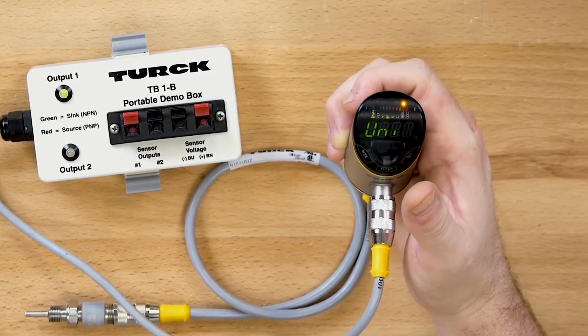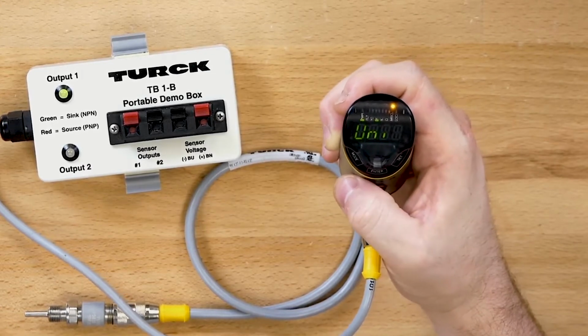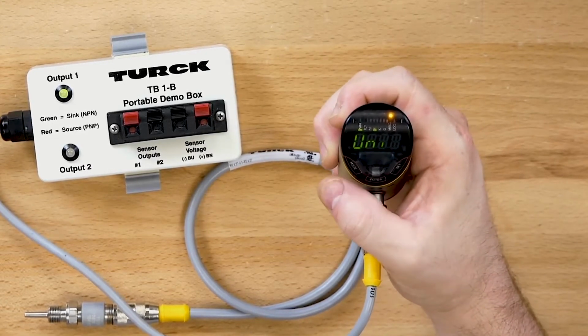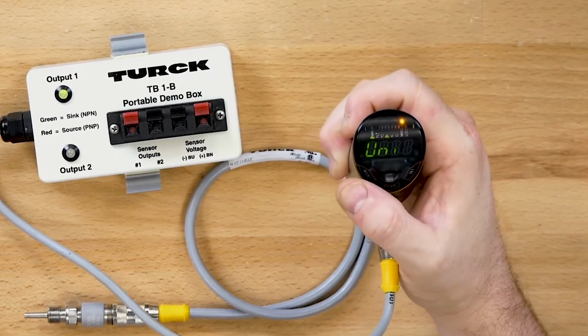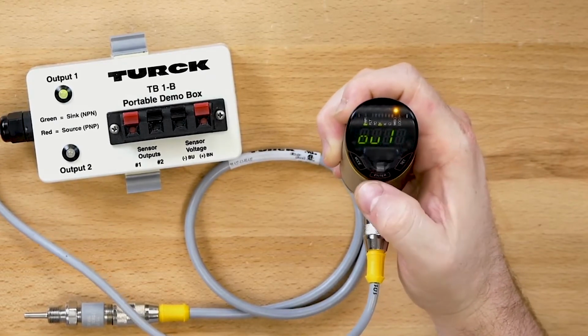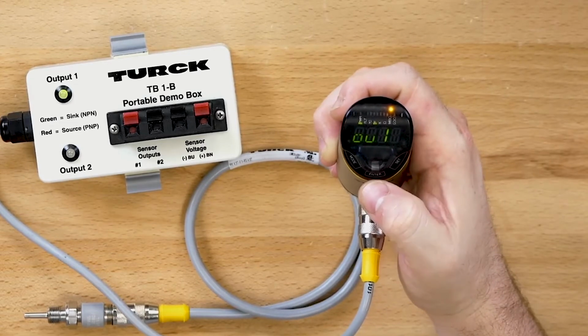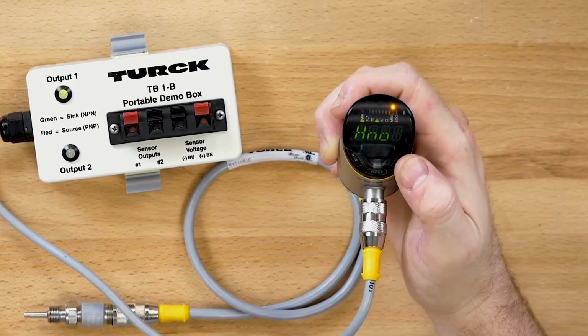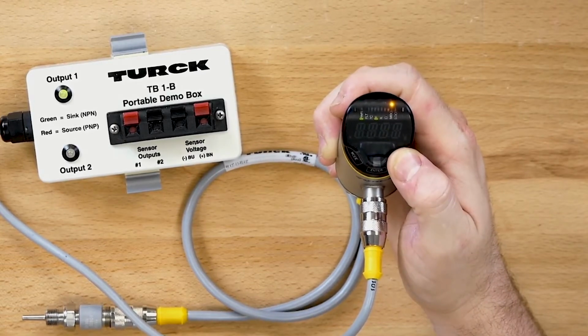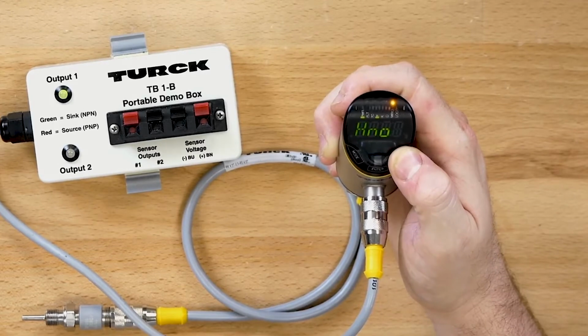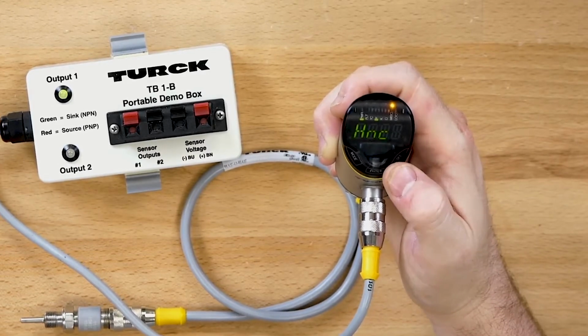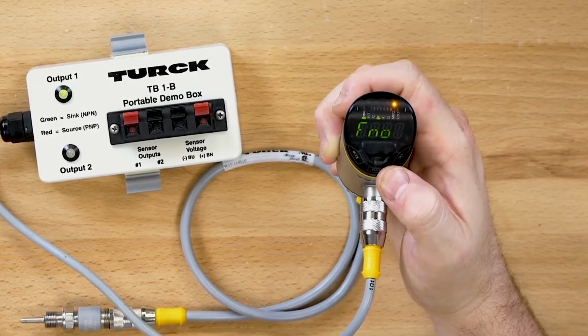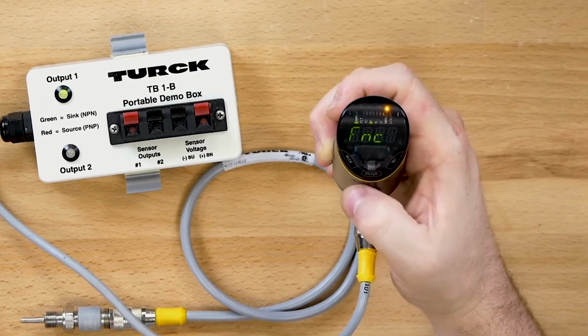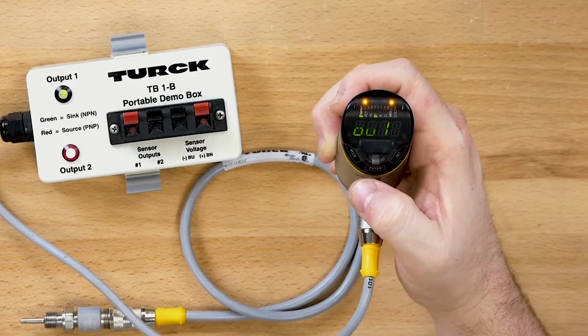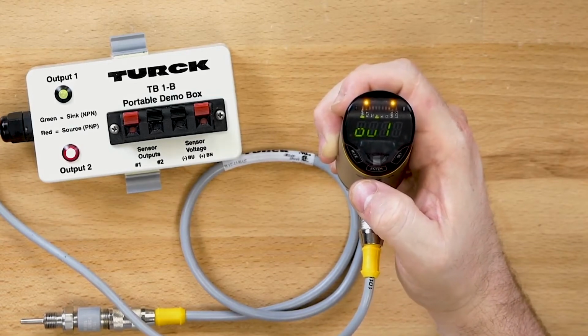With the temperature unit set, let's put our sensor into window function mode. Again, using the Mode and Set buttons to navigate the menu, highlight Output 1, abbreviated by OU1. Click Enter. Holding the Set button for 3 seconds again until the display stops blinking. You can use the Mode and Set buttons to navigate the menu until you reach FNC. Click the Enter touchpad, and this now sets Output 1 to a normally closed window function.